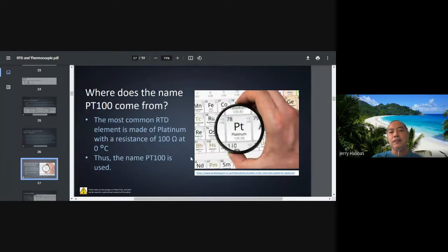Okay, so why is it called PT100? Where does this word PT100 come from? So the PT actually means platinum, no? Look at your periodic table, that's the symbol for platinum, PT. Then the 100 means 100 ohms at 0 degrees centigrade. Okay? So there is also PT1000. Of course it means that a PT1000 is made of platinum and it has 1000 ohms at 0 degrees centigrade.